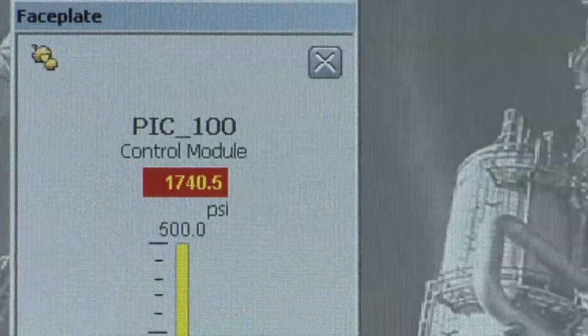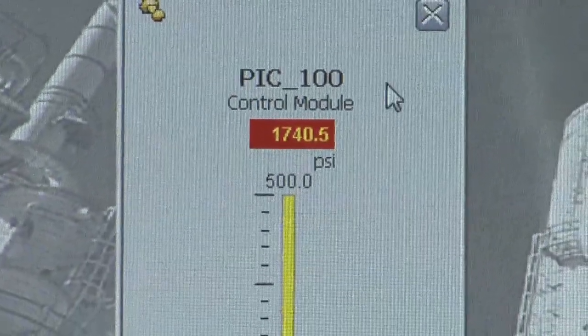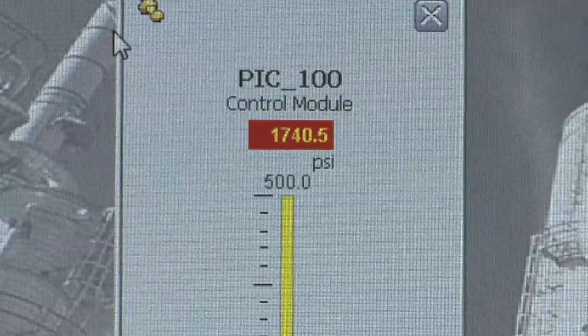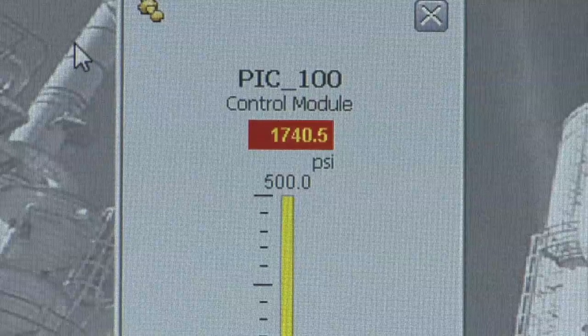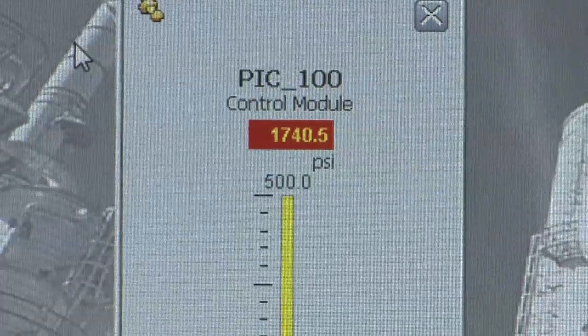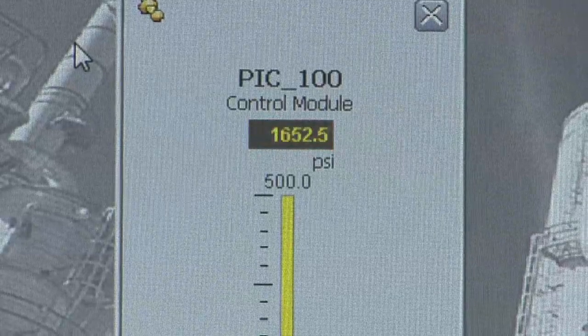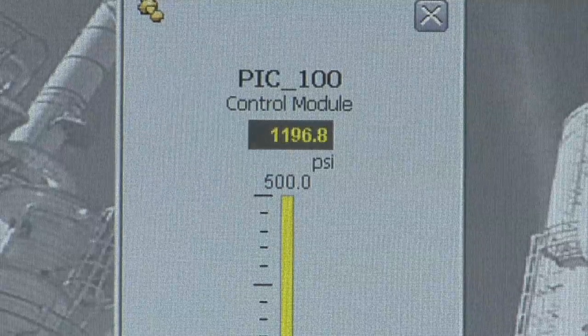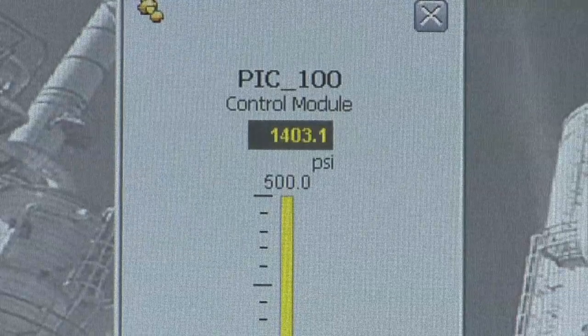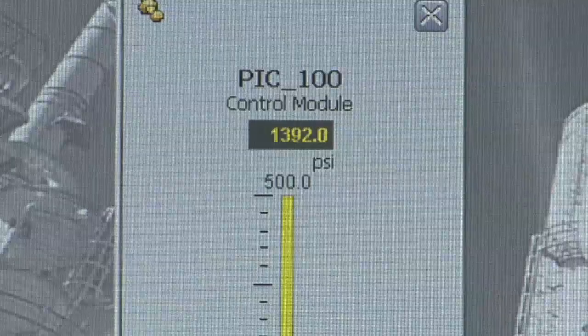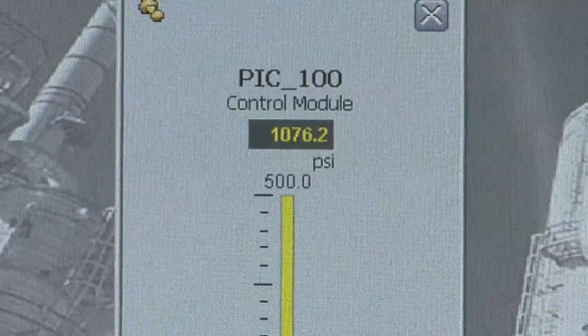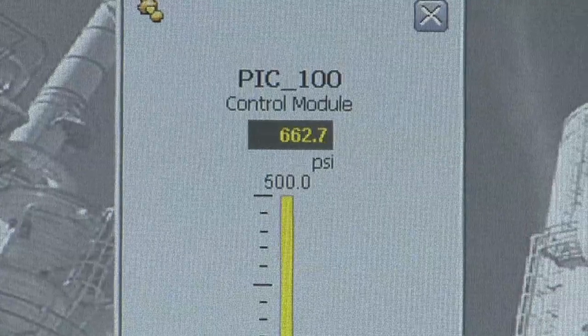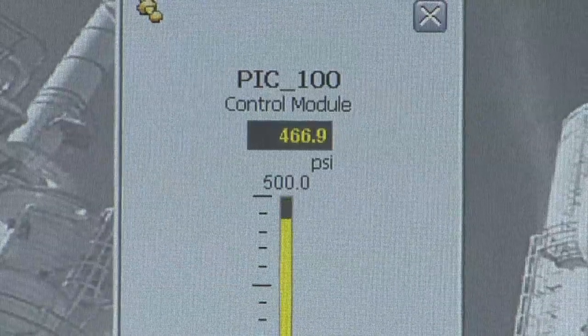Now if we go back over here, we'll see that this has actually turned red, showing us that it is a bad value entirely, and the operator now effectively has no idea what's going on in the system. Chuck has now lowered the psi, and we're back within range of the capsule — but as you can tell, we're still above the scale. The value's still dropping, and there we are.